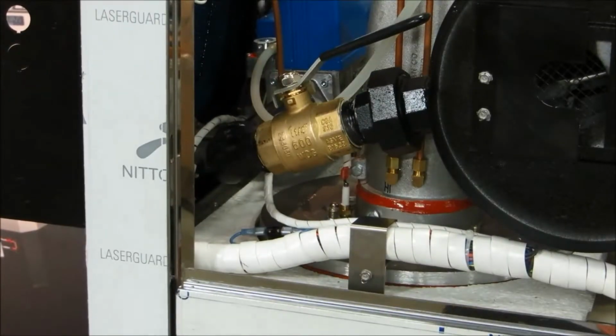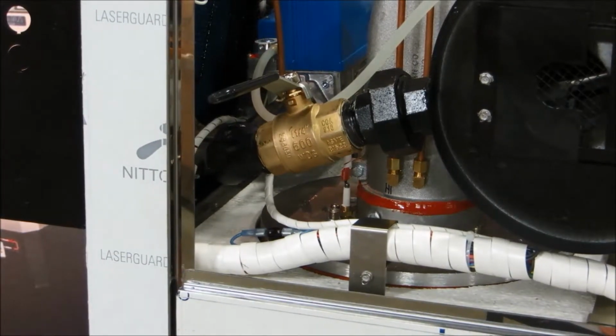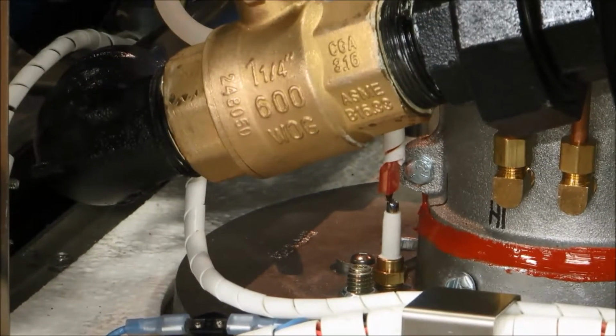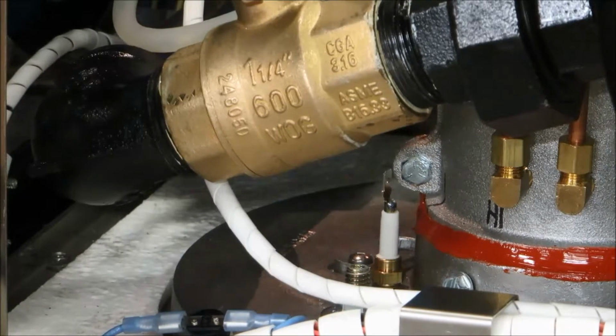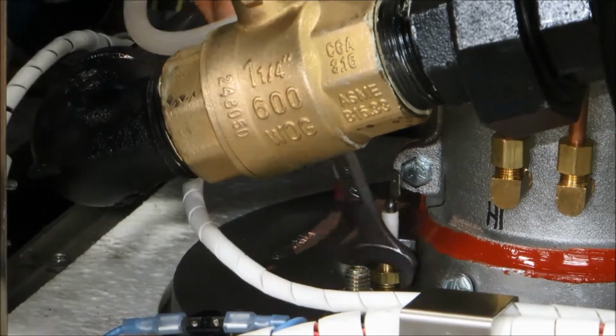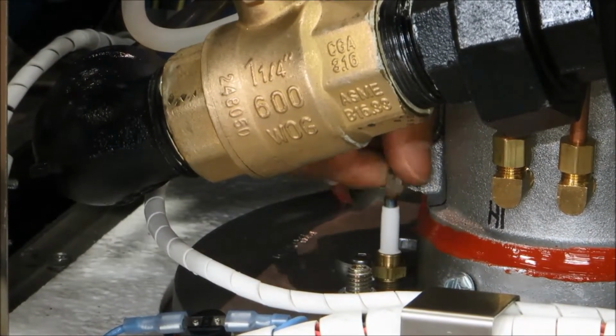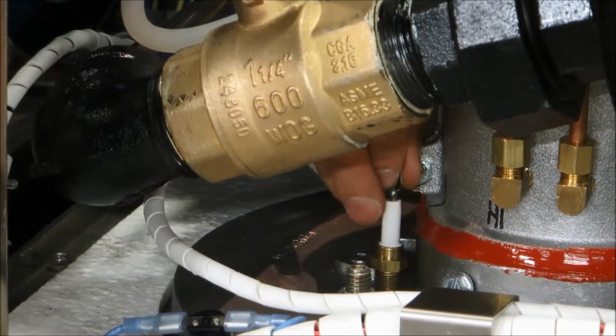Close the firing valve on the gas train. Remove the fast-on connector on the flame sensor. Using a 1/2-inch wrench, loosen the flame rod and remove it by gently pulling it vertically upwards. If cleaning of the flame rod is required, use steel wool, never use sandpaper.